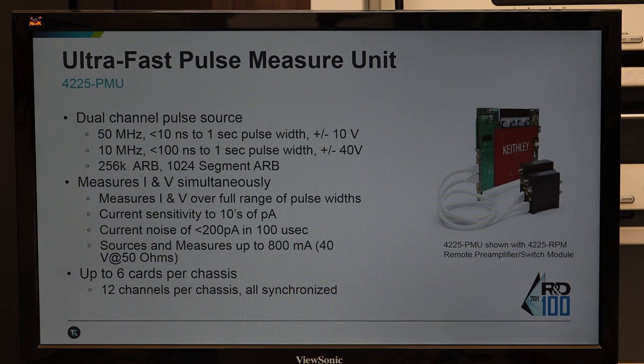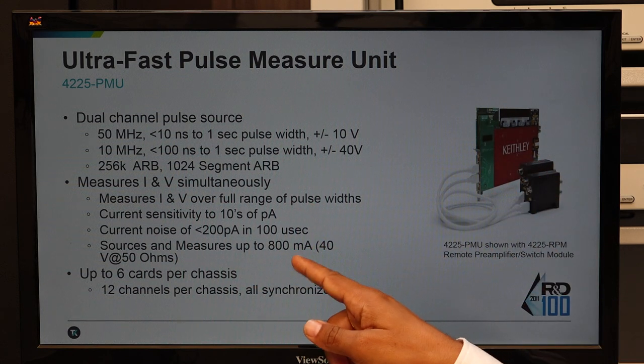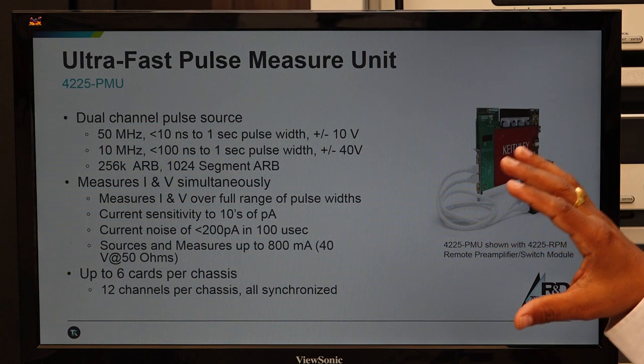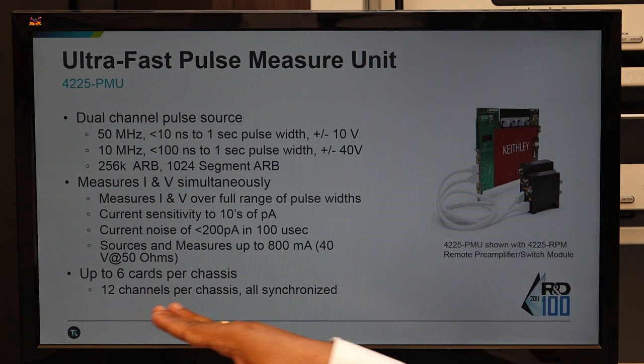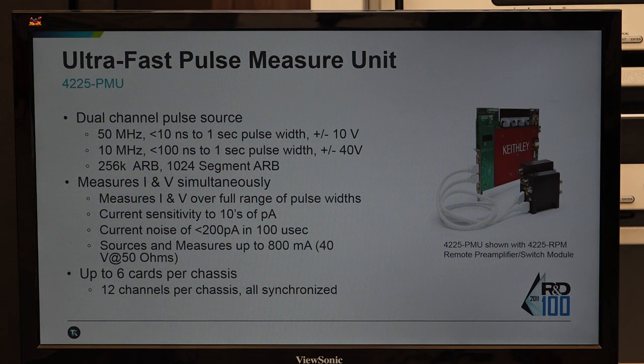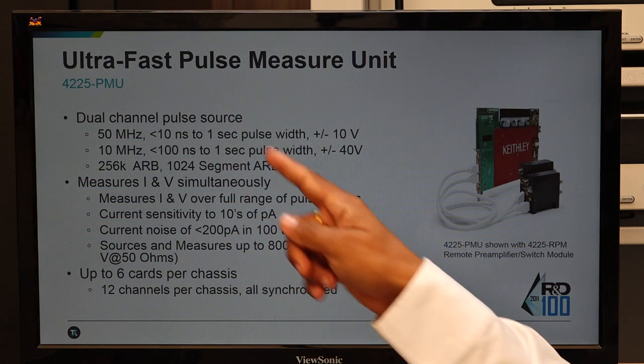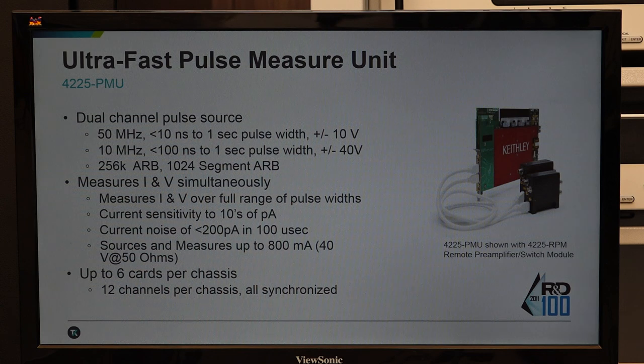Generally, pulse generators don't support current more than a milliampere. But for fast IV measurement on materials and devices — for example, pulse IV characterization of a MOSFET where current can be hundreds of milliampere — it is not possible to use any standard pulse generator. Using this instrument supporting 800 mA is very useful. We can add 12 channels into one box of parametric analyzer. For upcoming MEMS or memory technologies with arrays like 2×2, 4×4, 8×8, very accurate pulse sourcing with built-in current measurement is needed, easily fulfilled with 4200 having multiple 4225 PMUs.